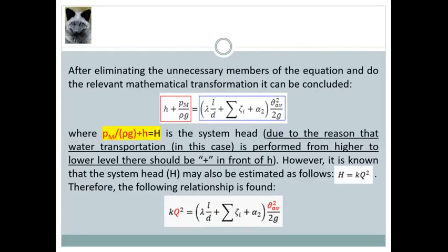After eliminating the unnecessary members of the equation and do the relevant mathematical transformation, the following equation that you see below is obtained, where Pm divided by the multiplication of rho and G plus H, the small one, is the system head, due to the reason that water transportation in this case is performed from higher to lower level. There should be plus H. There should be plus in front of H. This is something important that should be taken into account.